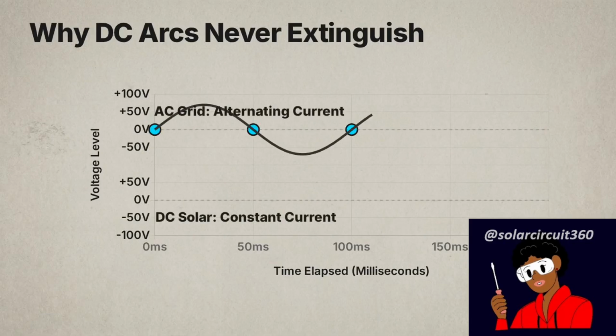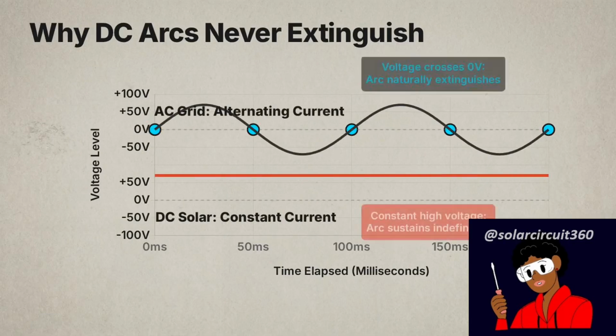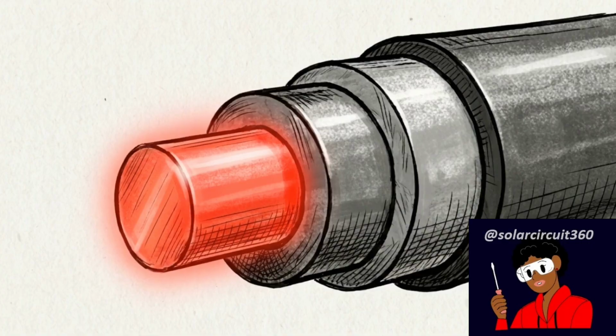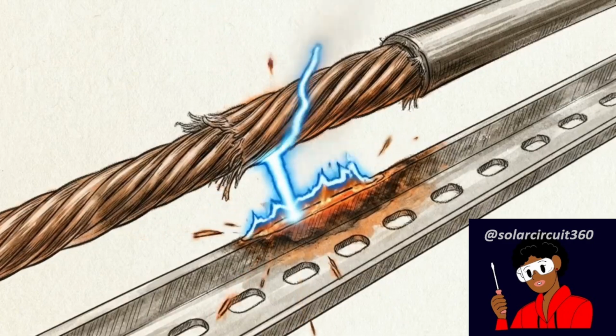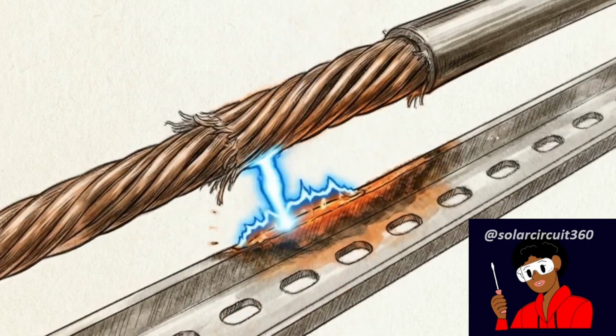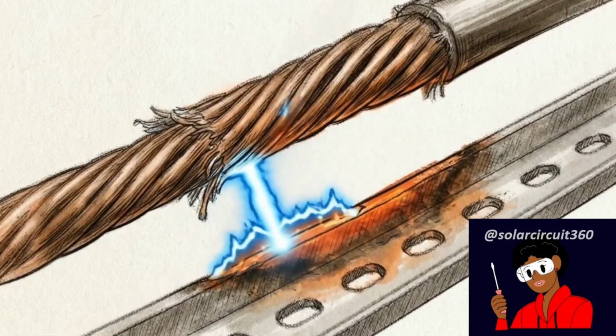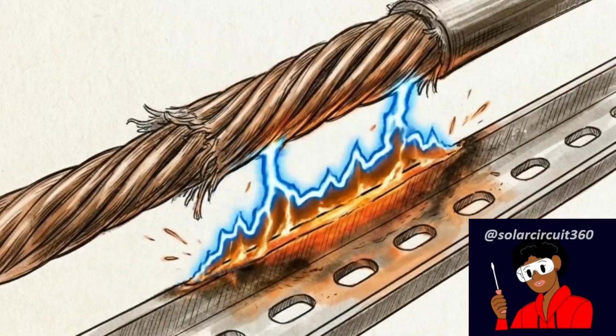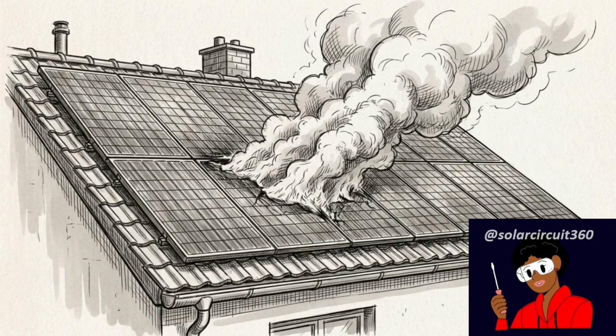Standard AC grids have a zero crossing that naturally extinguishes arcs as the voltage alternates. DC solar systems lack this cycle, providing a constant flow of energy. Without a zero crossing to interrupt the path, the localized heat from a leakage fault can transition into a permanent, self-sustaining arc fault. Microscopic leakage provides the mathematical foundation for localized heating, which can eventually escalate into a rooftop fire.